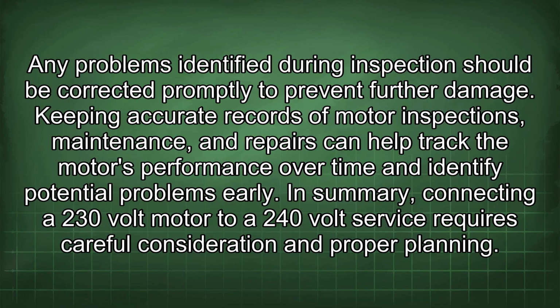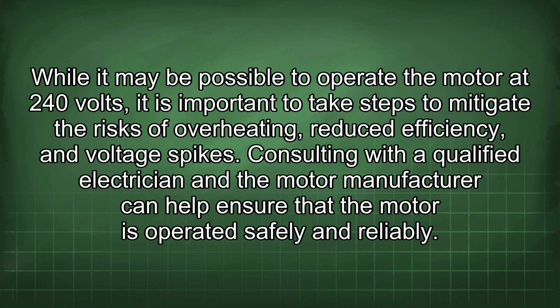Keeping accurate records of motor inspections, maintenance, and repairs can help track the motor's performance over time and identify potential problems early. In summary, connecting a 230-volt motor to a 240-volt service requires careful consideration and proper planning. While it may be possible to operate the motor at 240 volts, it is important to take steps to mitigate the risks of overheating, reduced efficiency, and voltage spikes. Consulting with a qualified electrician and the motor manufacturer can help ensure that the motor is operated safely and reliably.